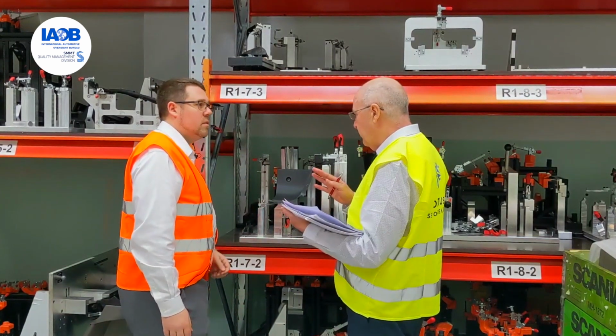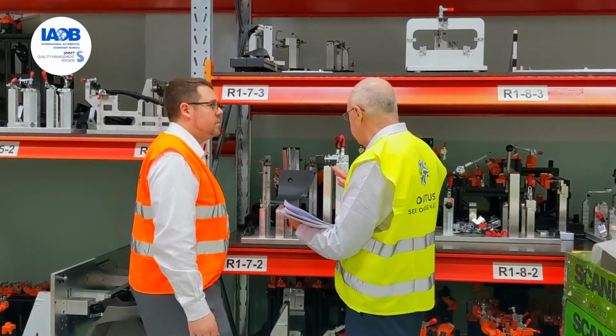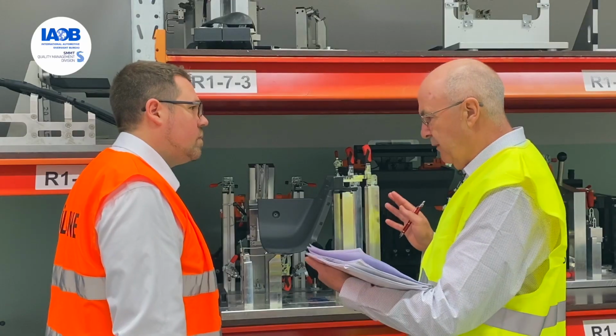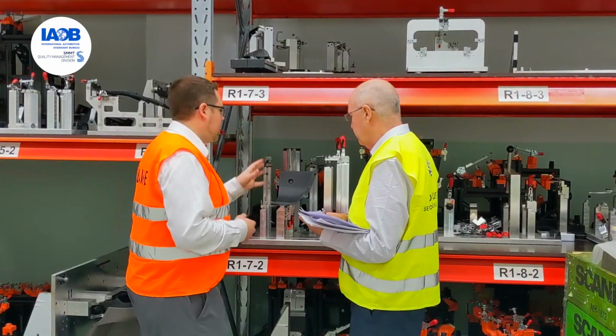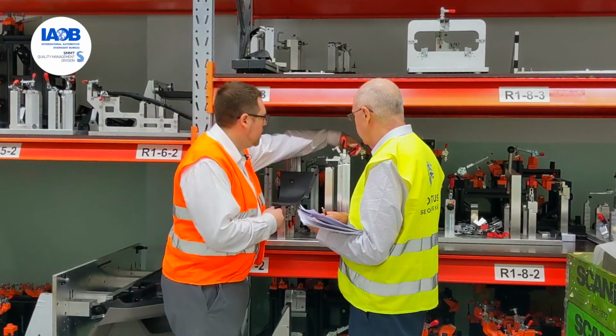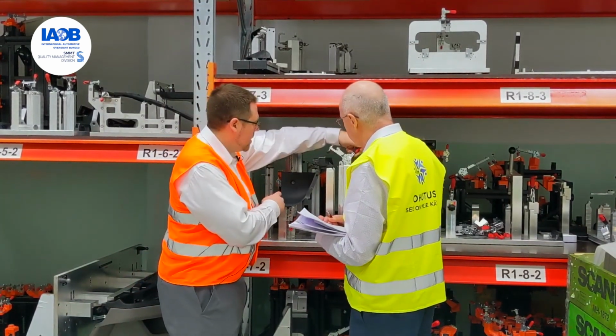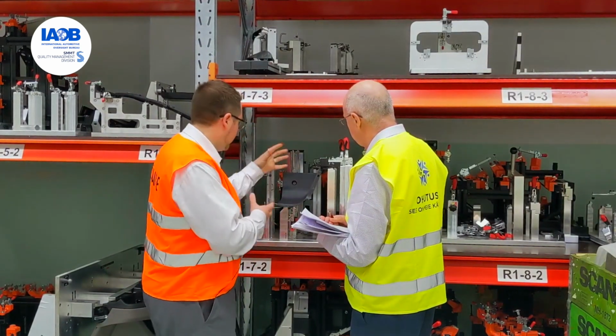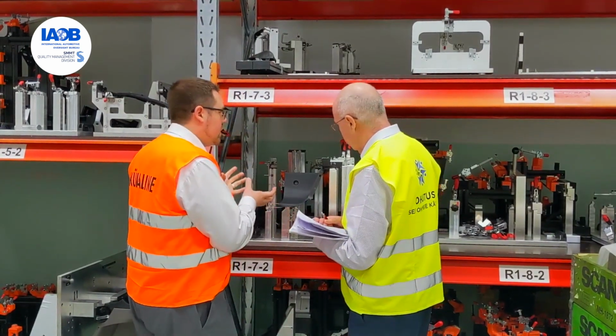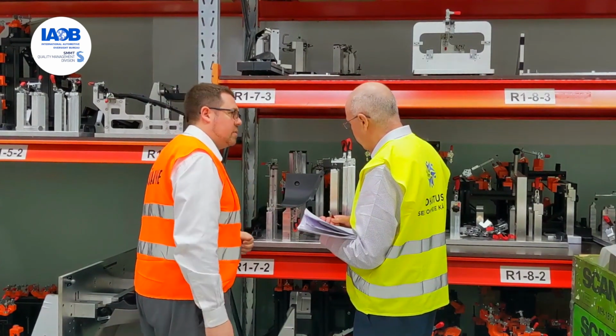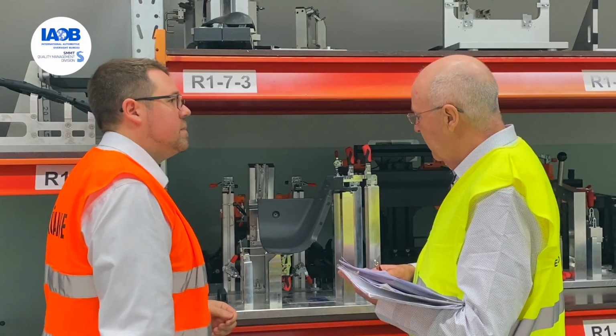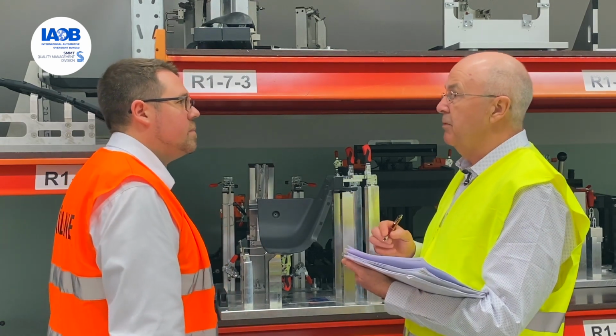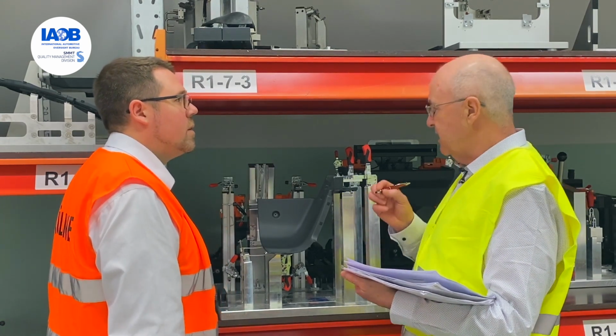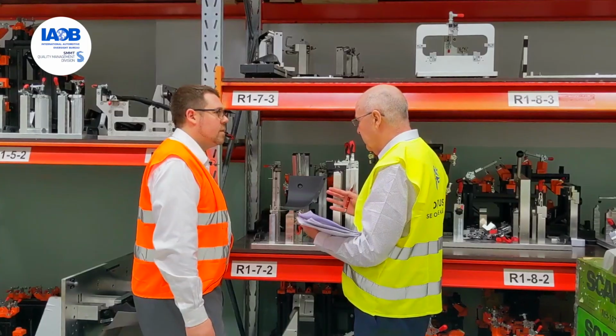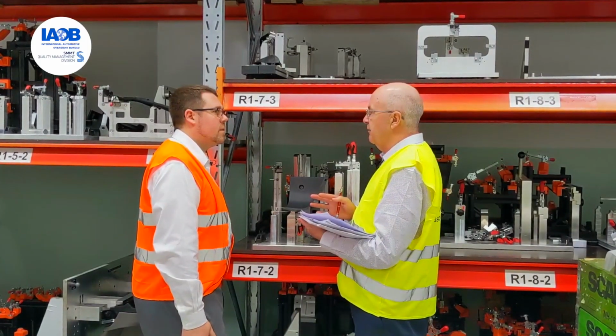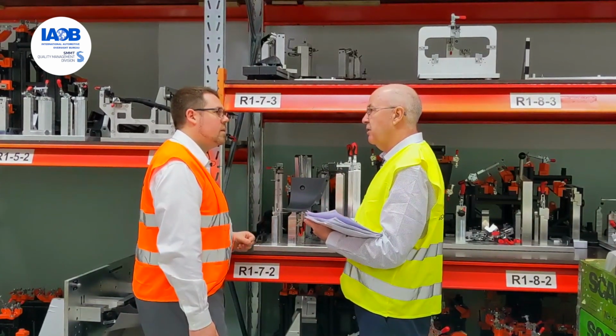Right, we'll come back to the calibration aspect. What about the maintenance of the jig itself? Every time we put a part in, before we put it in, we check and make sure there are no nicks or anything on these levers that hold it in place, and nothing damaged on the fixture itself. Right, okay. That to me is going to be a problem in this audit, because this is a measurement fixture, so I do need to see records of calibration for this. I'm going to be recording that as a non-conformity.